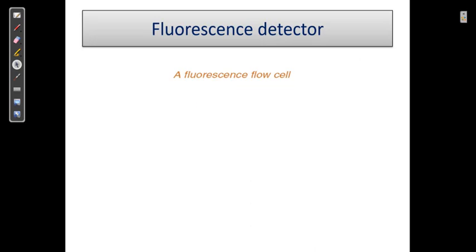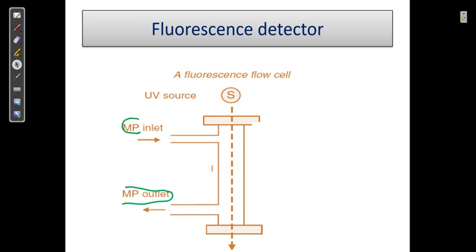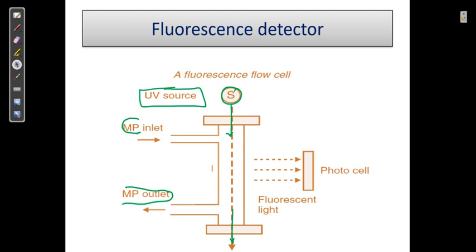Here is the flow cell diagram — this is our tube, our flow cell. Mobile phase enters from one side and exits from the other. A UV light source illuminates the cell; this is monochromatic light passing through the mobile phase.